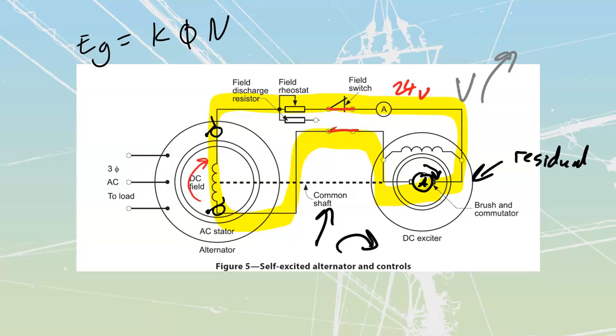Once we actually close in, this circuit opens over here. Now my field switch is fully closed in. That means that little connection over there is going to be open. There's no current flow through the field discharge resistor, and all the current flow is through these yellowed-over lines here, meaning my DC exciter is sending DC to my DC field over here, which then allows me to generate AC off of here.